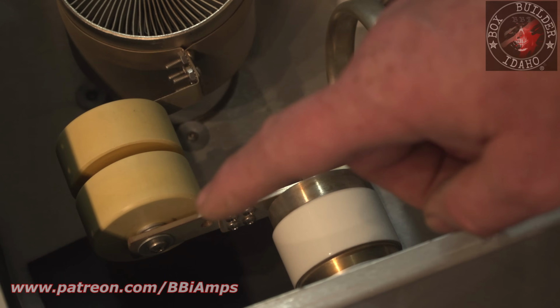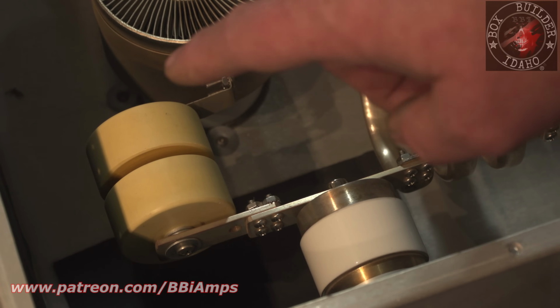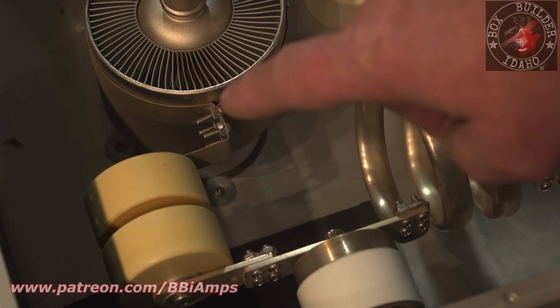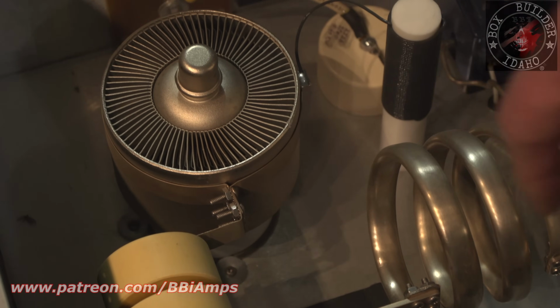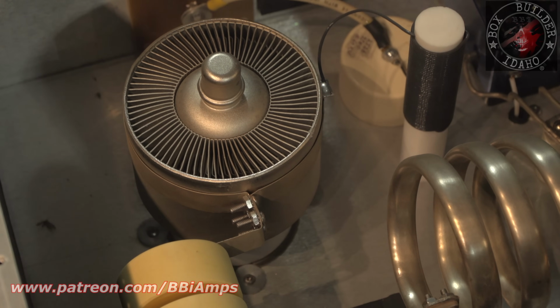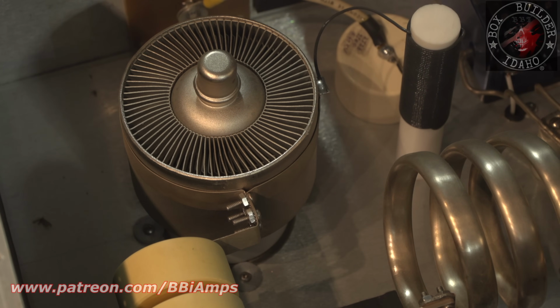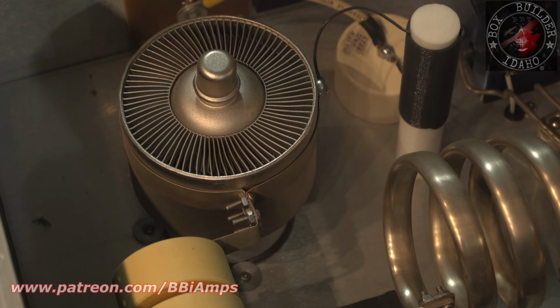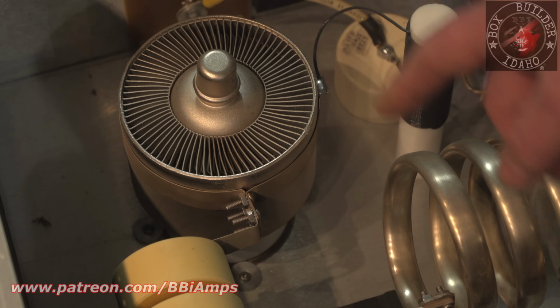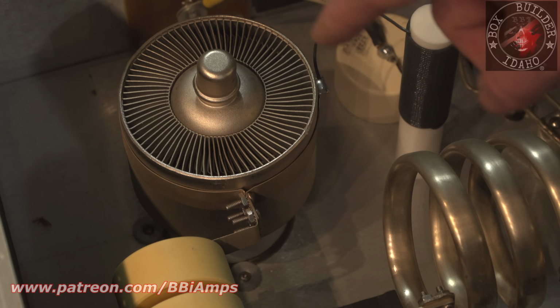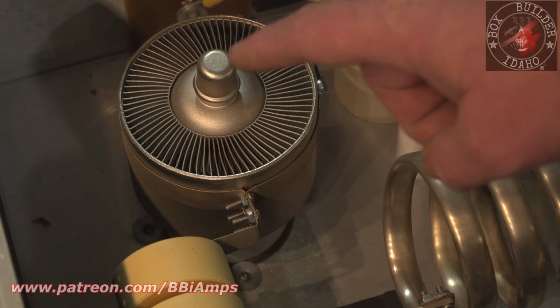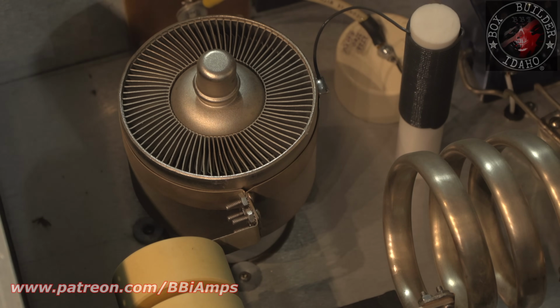So the tank coil's hooked up. Look at the interface surfaces between the blockers. Look at the strap that goes around the anode. No, that's not a piece of unknownium metal hose clamp holding it down. This is a piece of copper that was hand cut to the exact length it needed to be to go around the anode of the tube. That's 7 years worth of operation.